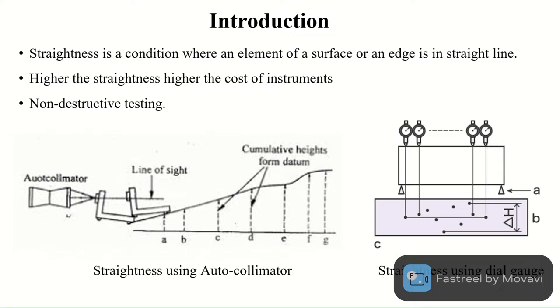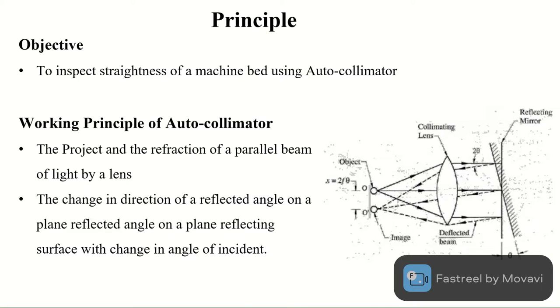In the present slide, I have defined straightness and different non-destructive methods to measure it. Straightness is a condition where an element of a surface or an edge is in exactly a straight line. Higher straightness of any instrument leads to higher cost of that particular instrument. For measuring straightness, generally three methods are used. The first one is the autocollimator for measuring straightness of a large surface. Second and third are dial gauge and spirit level for measuring straightness of a small surface. Today, we are going to use the autocollimator for the measurement of straightness, so our main objective is to inspect the straightness of a machine bed using the autocollimator.